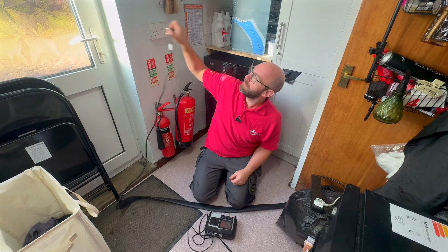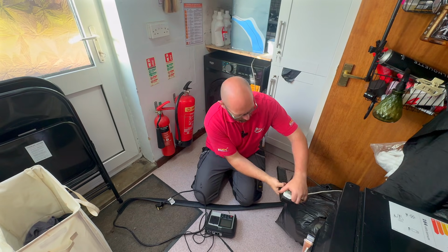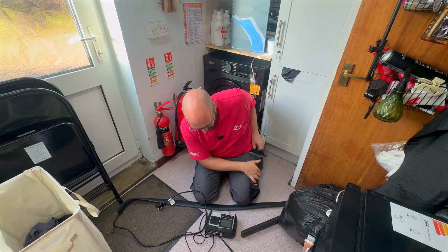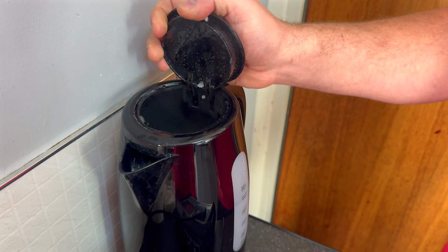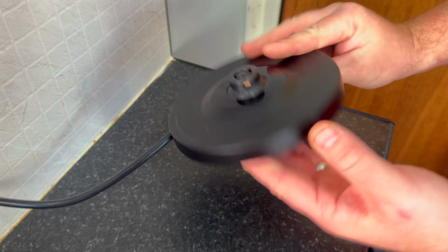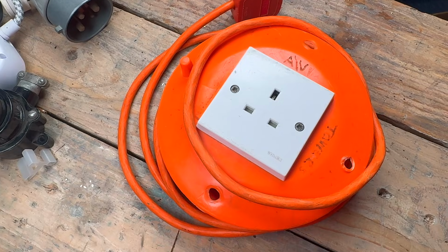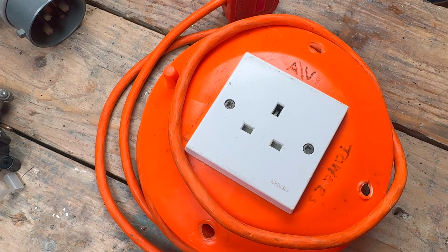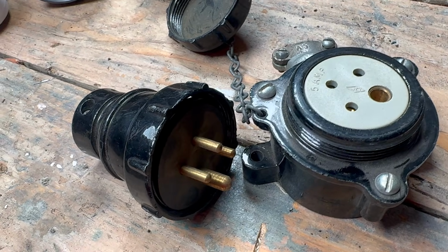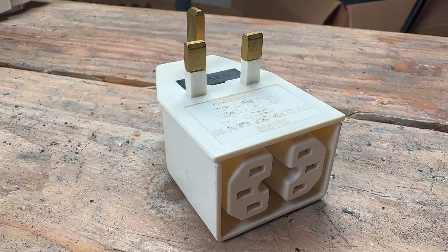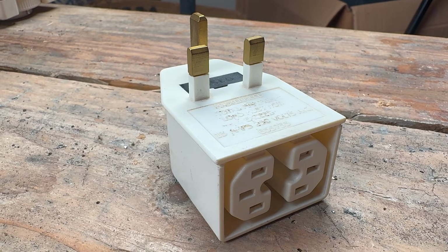The duty holder can delegate tasks, but they can't delegate responsibility. If they appoint someone to carry out inspection and testing, they must ensure that that person is competent. They must also recognise that not all equipment meets the same standards. Equipment of unknown origin, custom-made equipment, or equipment purchased from outside the EU may not meet recognised safety expectations, and the duty holder must factor that into their risk assessments.